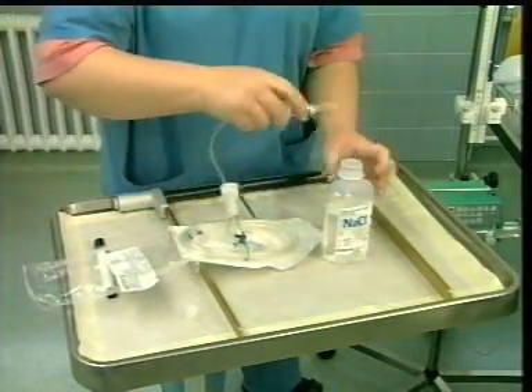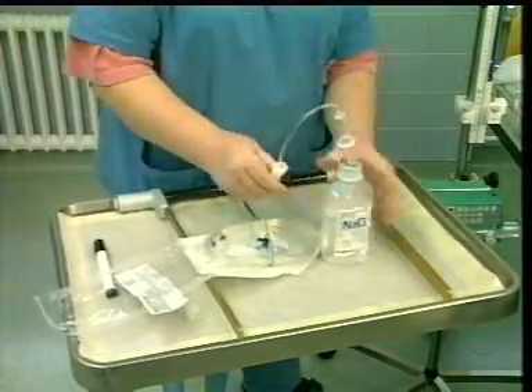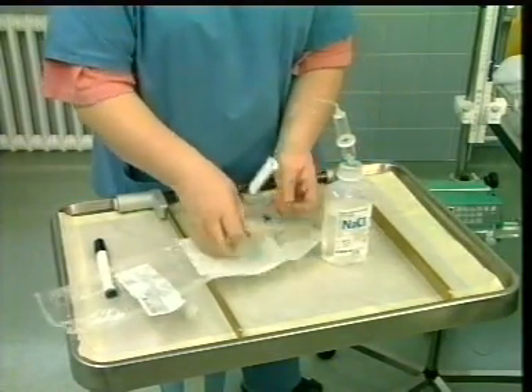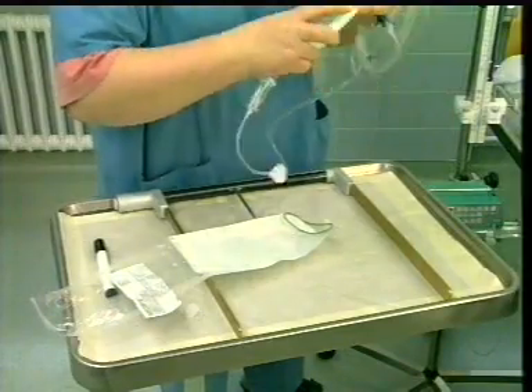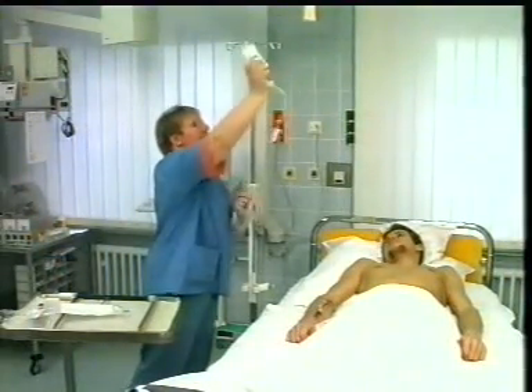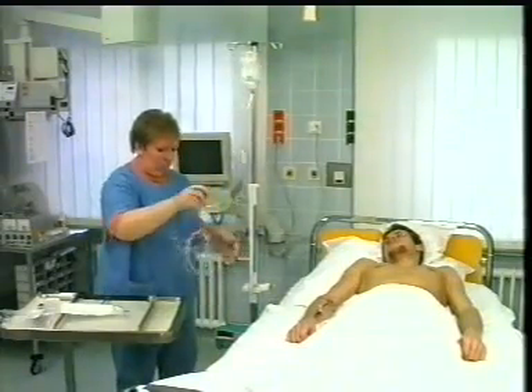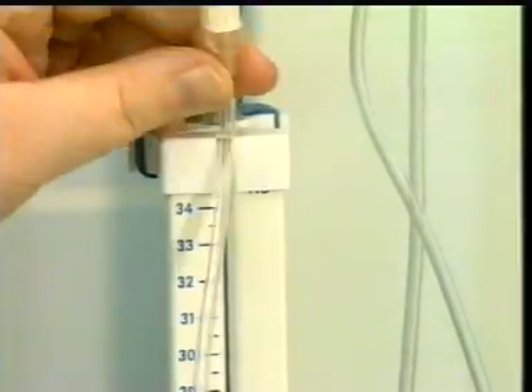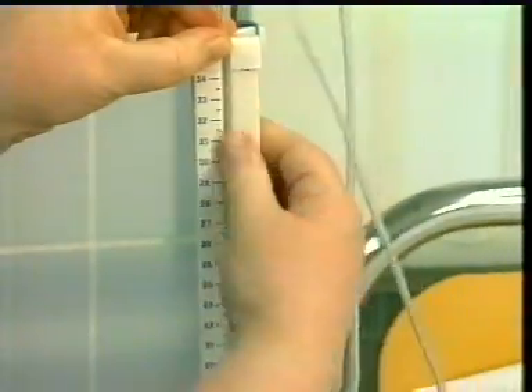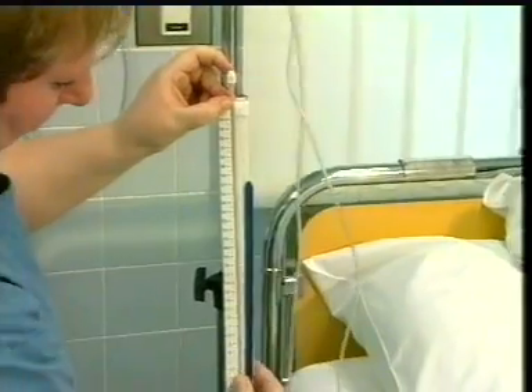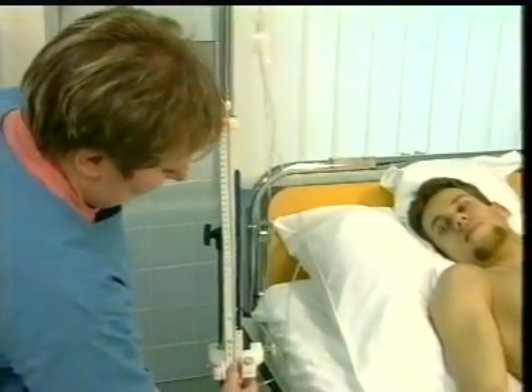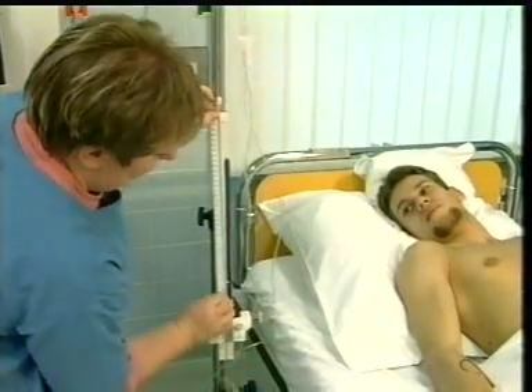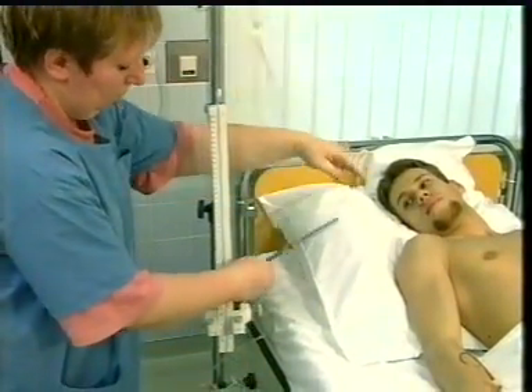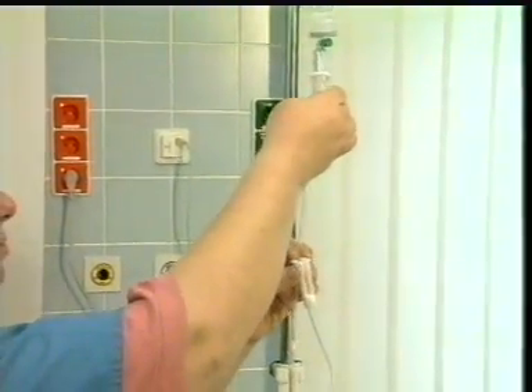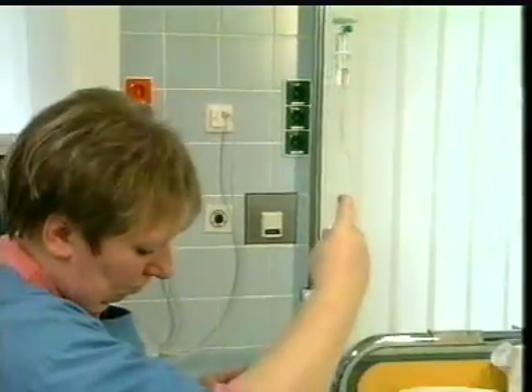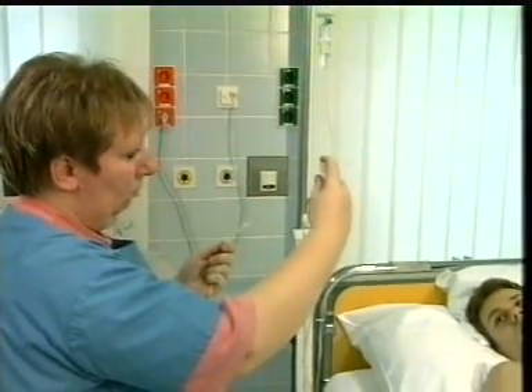The infusion system is connected with the saline solution. The roller clamp of the infusion system is closed and the infusion bottle is suspended. The connection tubing to the patient is attached at the roller clamp. The manometer tube is inserted in the holder of the manometer scale with the filter end pointing upwards. The whole infusion system must be vented. To do this, the roller clamp is opened and the three-way stopcock is set so as to allow the venting.